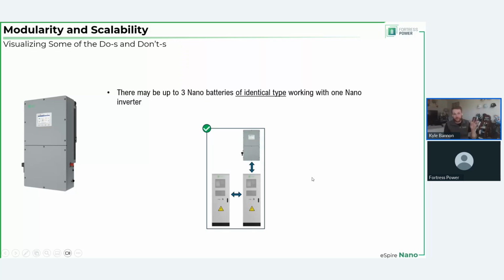We can put up to 3 batteries of identical type to a single inverter, right? So we haven't even talked about the battery side yet. We'll get into that in a minute, but essentially there's a 40 kilowatt hour option and a 60 kilowatt hour option. As long as they're identical type, we can put up to 3 of those to a single inverter. So the smallest we're talking would be a 30 kW, 40 kilowatt hour. The largest with just one inverter, no parallel inverters, would be a 60 kW, 180 kilowatt hour. Yes, that's correct. So that's a pretty wide range for working off of just one hybrid inverter.